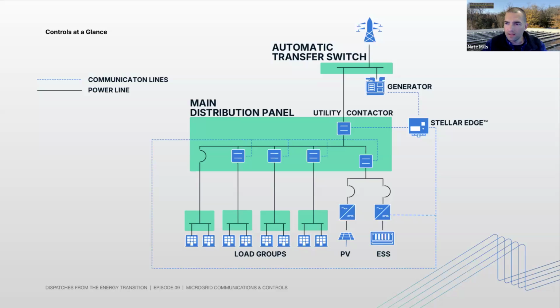Okay, that is in quotes, and so I am assuming that was pulled from a reference somewhere. But there are many references. So I guess we put it this way. If we're off grid, and so this is operating like any off grid system, there will be some requirement for how the system responds to faults, right? Maybe the battery loses its communication with the utility contactor, right? That's an easy one, right? The line breaks somehow or becomes disconnected. Then the battery does not know what state the utility contactor is in, which means that it's not safe to operate it in grid forming mode. So it'll fall back to grid following mode.